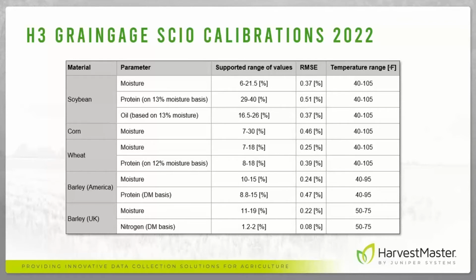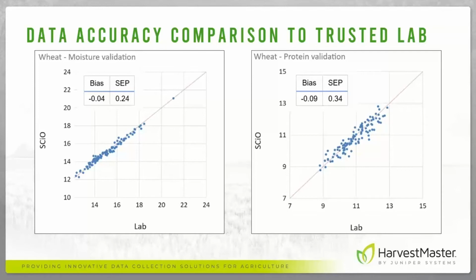So data-wise, really interesting. This first slide was taken when a bunch of samples were used and a calibration was created. In this case, it was a calibration for wheat moisture and wheat protein, built by SCiO. After that calibration was built, they introduced samples that were foreign to that calibration. None of the samples you see on the screen right now were used in the data set to create the calibration. They ran them through the SCiO, and we also sent samples to a lab. Compared to the lab reference, we had about a 0.24 and a 0.34 standard error with almost no bias, and that's for moisture and protein on wheat.